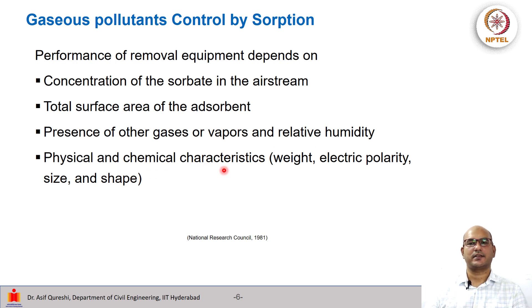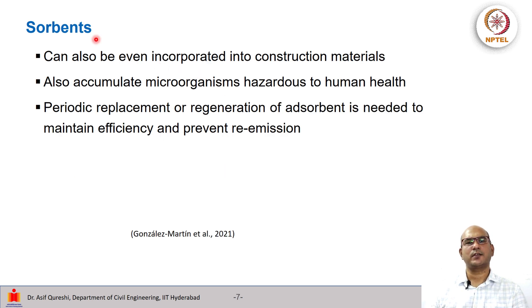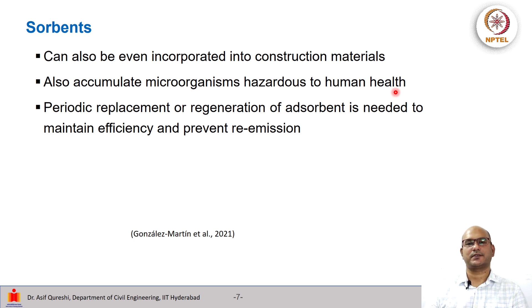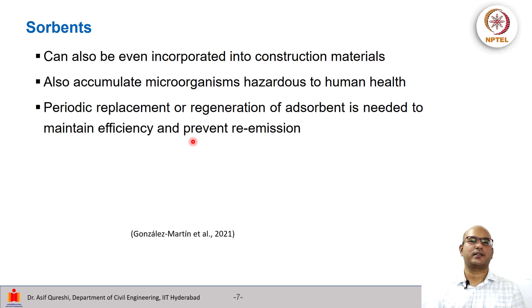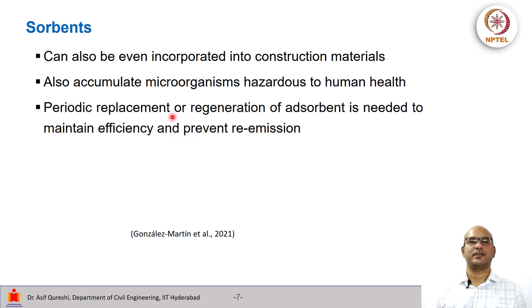Performance also depends on which gases or vapours are present, the relative humidity, and the physical and chemical characteristics of the sorbents. Sorbents can potentially be incorporated into construction materials, but they may also accumulate microorganisms hazardous to human health. Since pollutants are being attached to the surface, we need periodic replacement or regeneration of the adsorbent material to maintain removal efficiency and prevent re-emissions once the sorbent sites become saturated with pollutant.